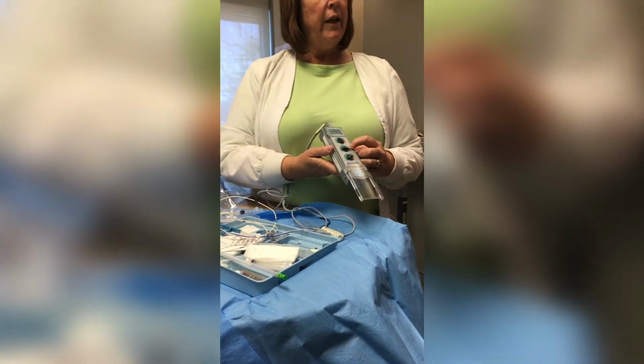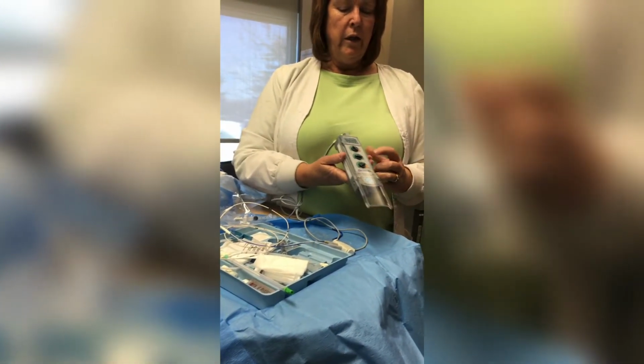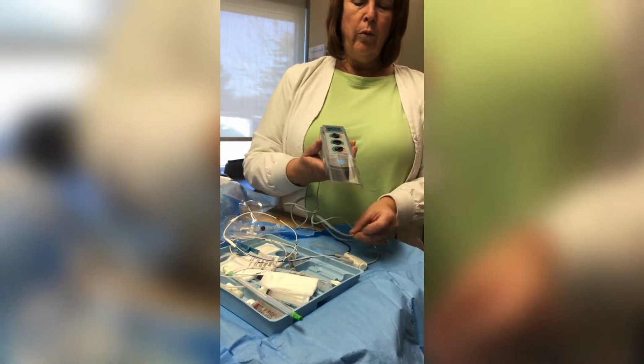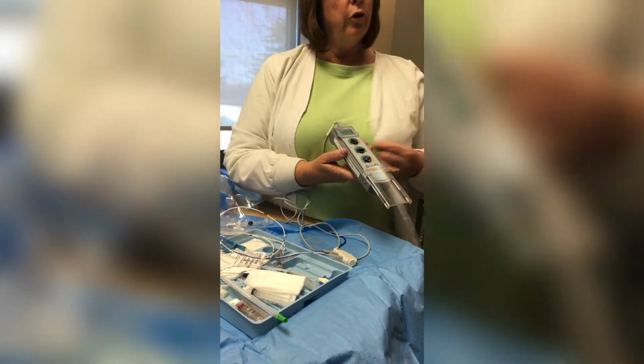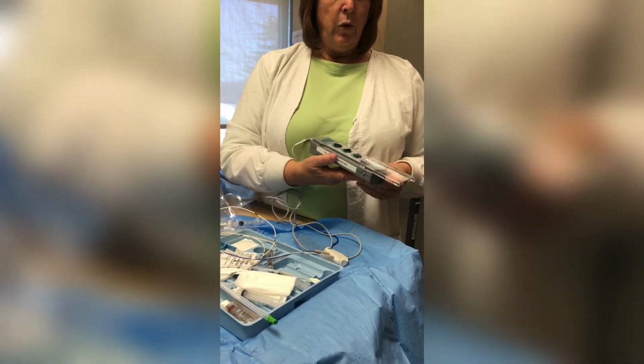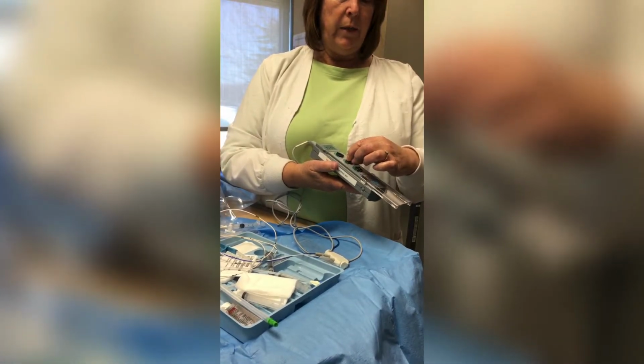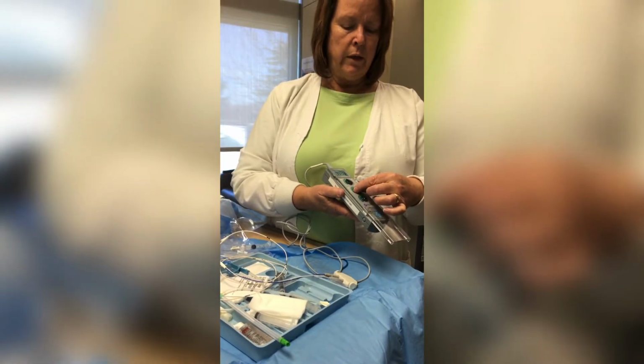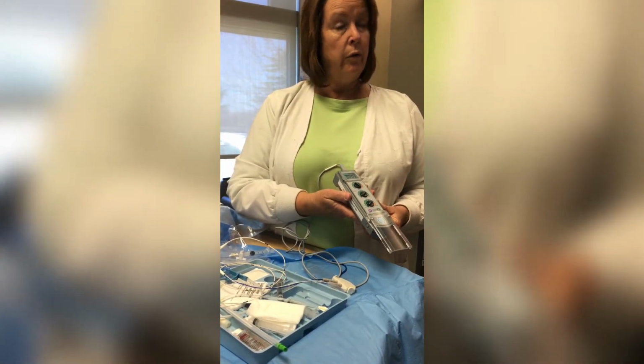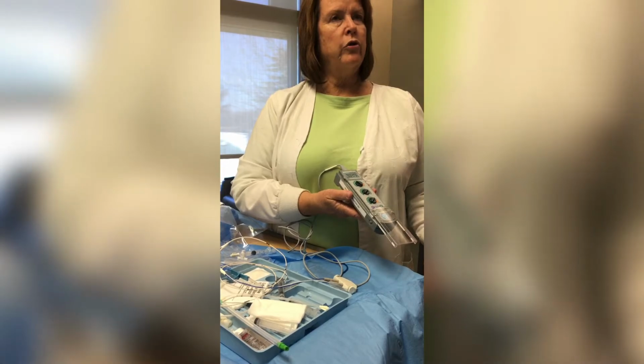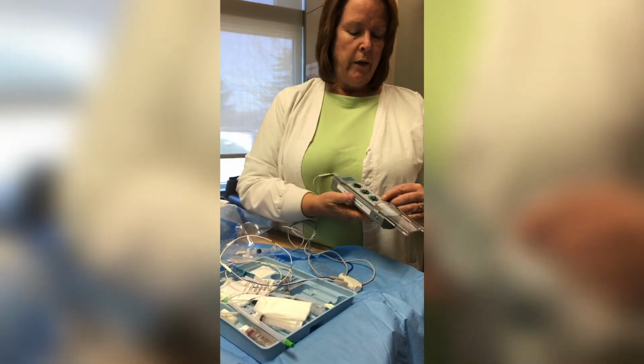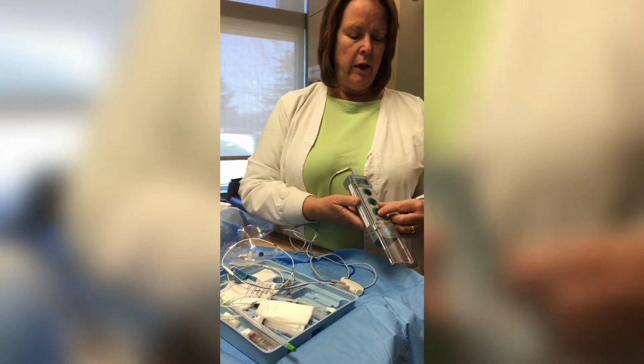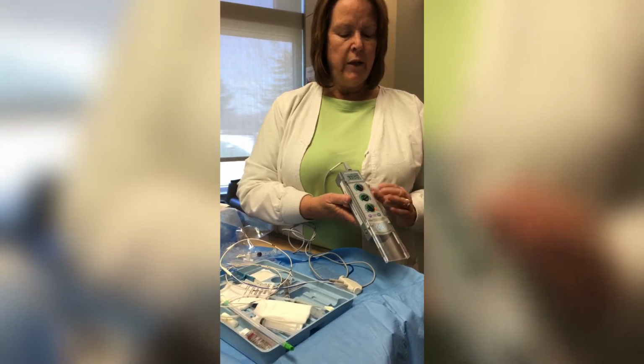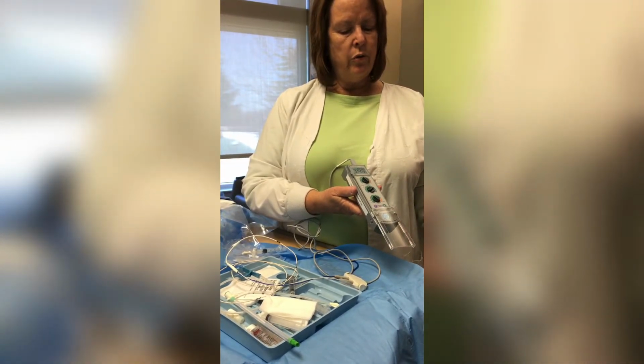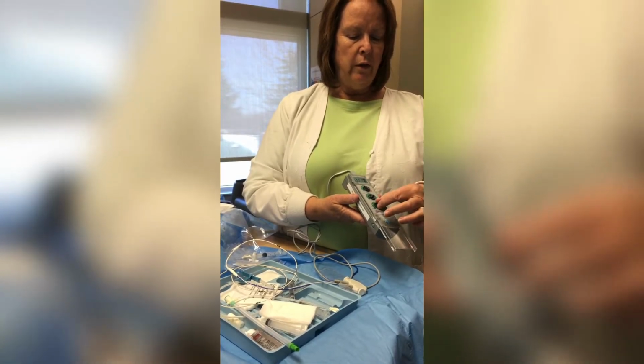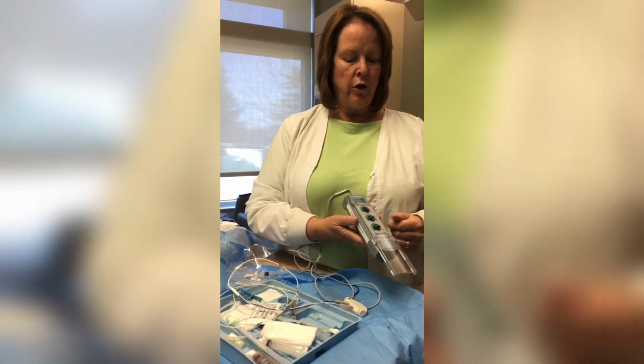And that's how much electricity is necessary to go through the pacemaker to cause the heart to contract when it's in the right place. Most of the time we put it pretty high at the beginning and then lower it depending on what's needed. So around 10 is an average amount, and it's all for the doctor's discretion, but that's an average amount. And then the bottom here is the sensitivity. This says how sensitive this pacemaker generator is to the patient's rate.